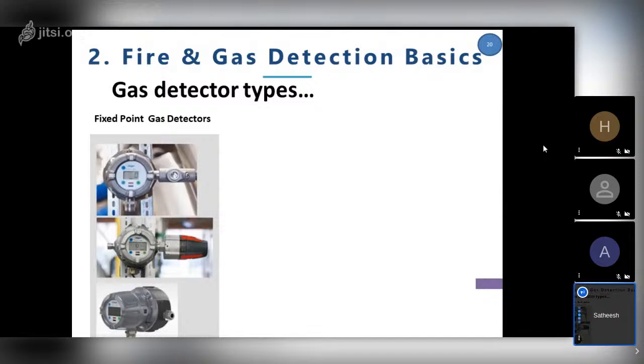And I mentioned here fixed point gas detectors. Why is that? Fixed stands for permanent gas detector. It means it is installed in one location where you think gas can be present under abnormal conditions, and we select the gas detector and you wire it and you give it power, so it is continuously giving the signal of what is the situation in that room. That is why it's called fixed. And why point? It doesn't cover the entire plant or area, it only covers that particular point.